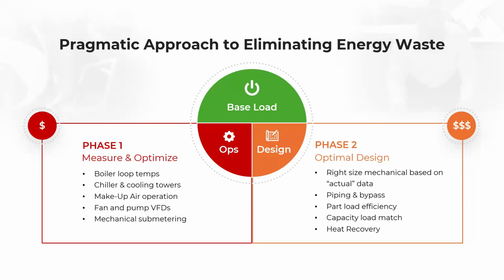And really optimizing around part load efficiency and matching the equipment that's running at the plant level to the load of the building. So if there are boilers in there, for example, trying to load up a boiler as much as possible before having to turn on the second one, rather than running 2 boilers at kind of half load. That is really an effective strategy. That's all part of this as well.